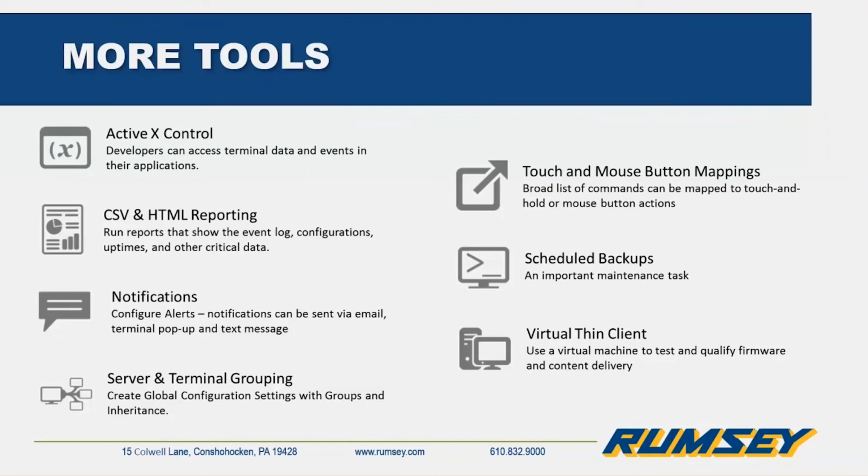Then I used that PXE boot, that pre-execution boot, to deliver my ThinManager firmware and my ThinManager content to a VMware image. This gives you the ability to fire up multiple virtual clients and test out your system long before you even have your hardware present and on site. So it's a very powerful tool.